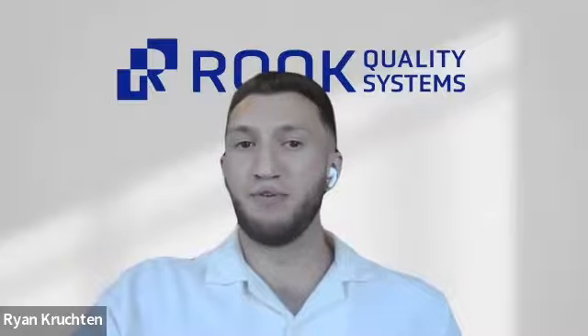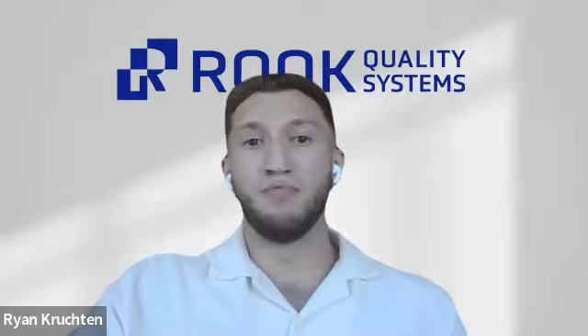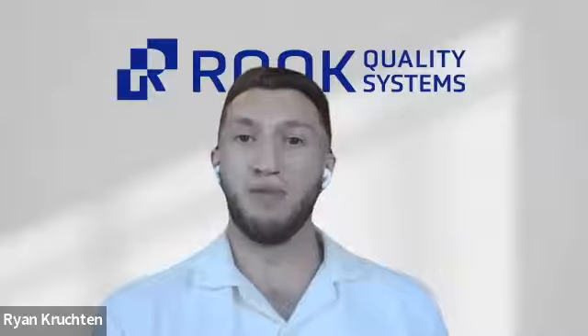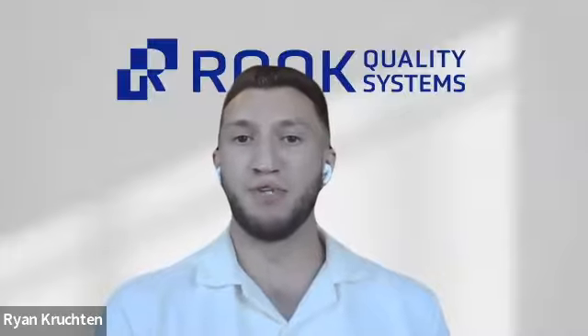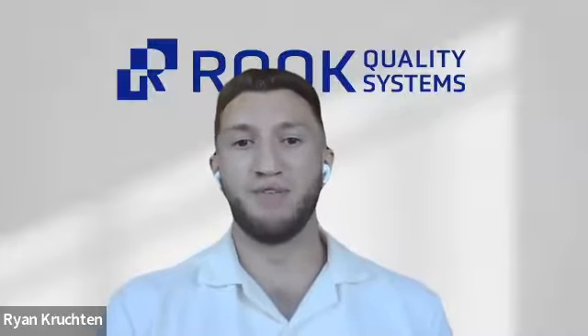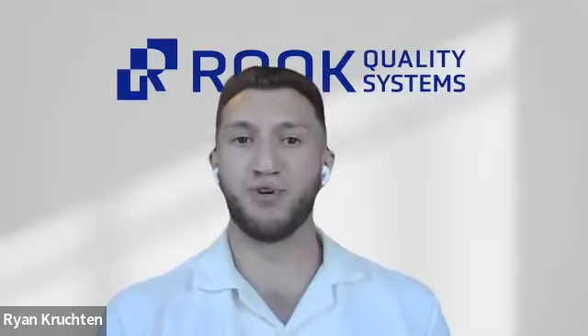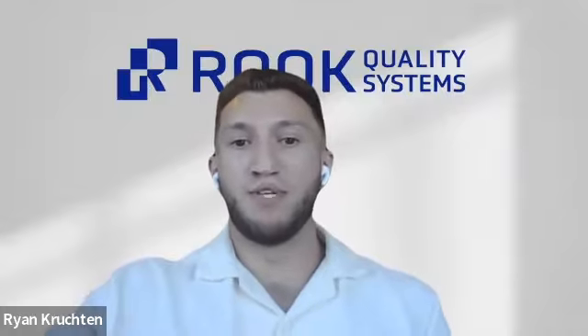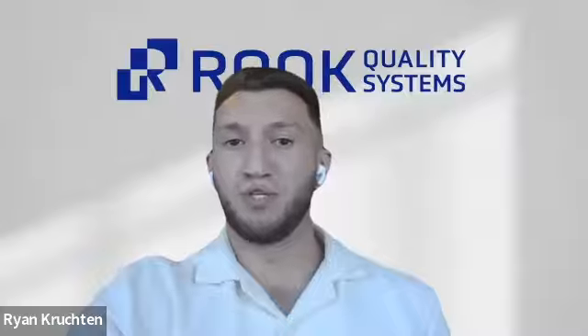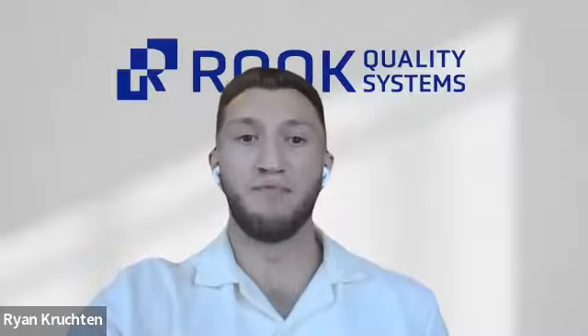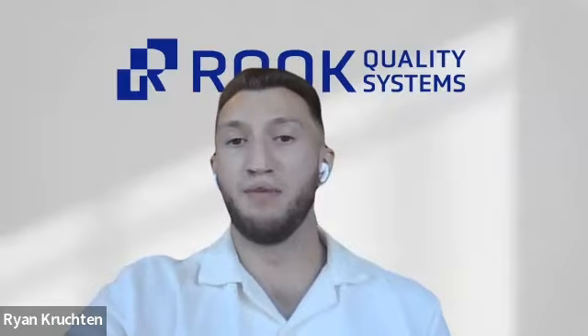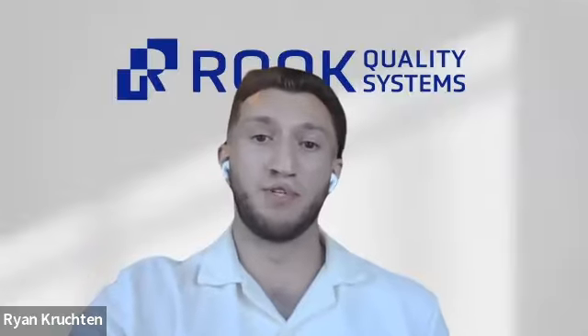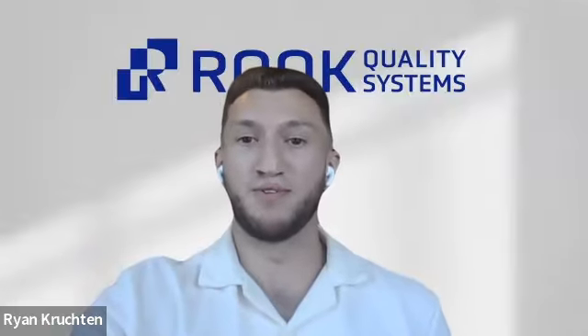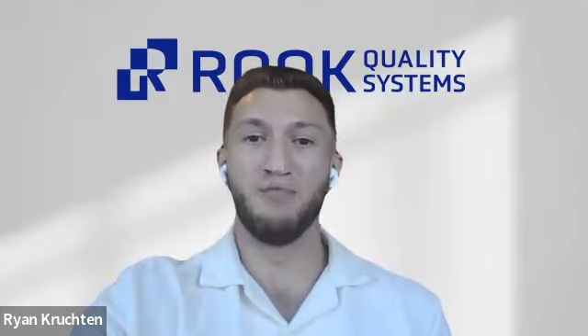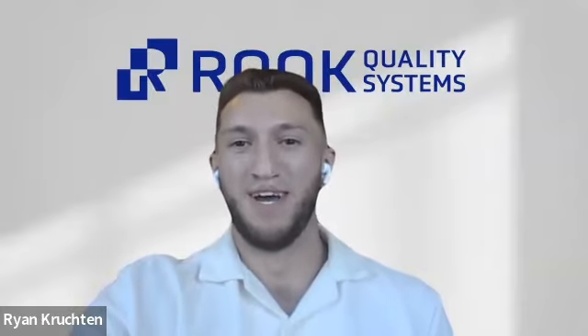So they talk about data integrity and security, the importance of using a secure data pipeline to prevent unauthorized manipulation, and verification and validation of data sets before and after training. The FDA is especially concerned with data lineage. You need to know where your data came from, how it's labeled or indexed, and whether it's been altered. So Reddit is not a good source for AI or ML medical device data, of course.